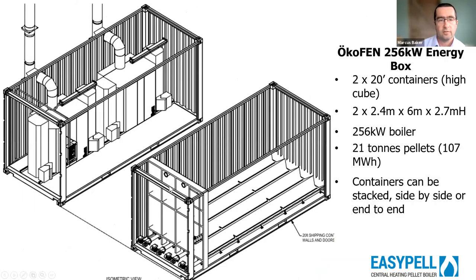So this is 256 kilowatts. We're now into two 20 foot containers. We've got our boiler plant room and we've got a dedicated pellet store, either with four or two augers, depending on the arrangement in here and cost preference. But we can get up to at least 21 tons of pellets in this container. So that does become a more significant load. We just need to have a think about the bearing on the ground, but we've now got over 100 megawatt hours of store. So we've really got a good amount of storage here.